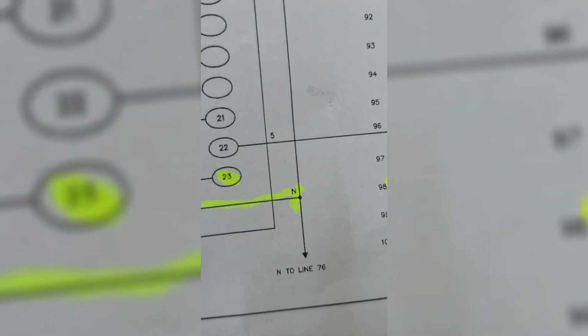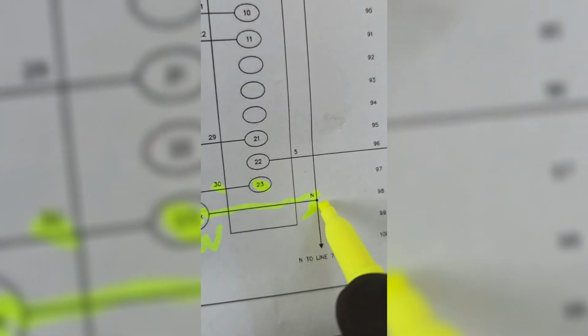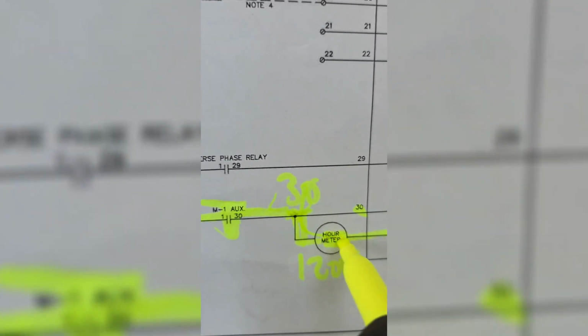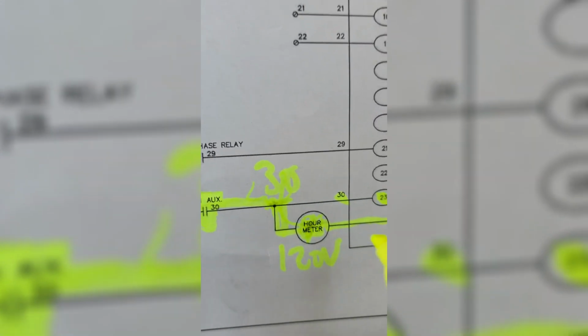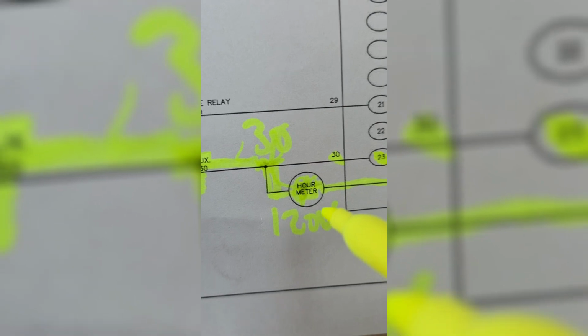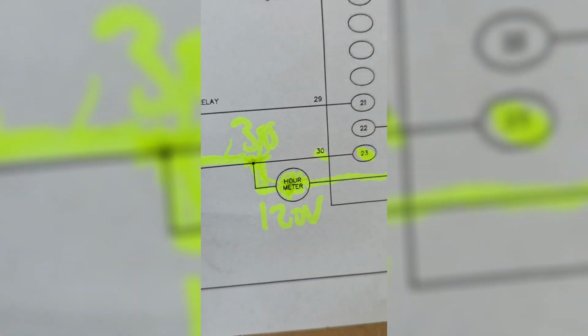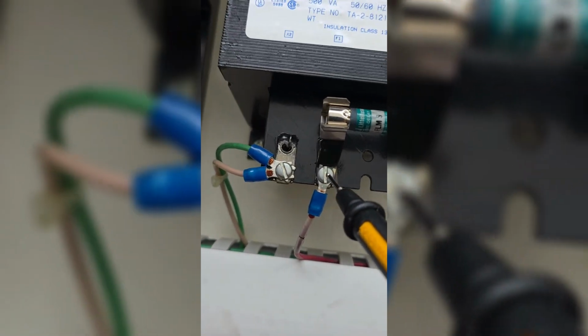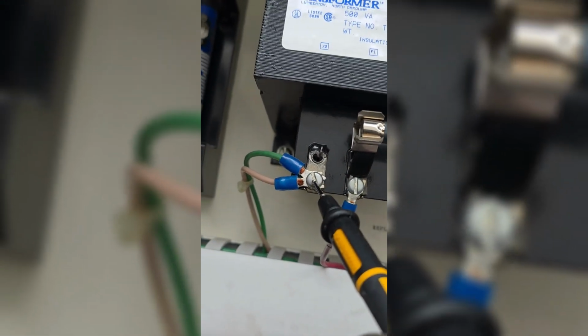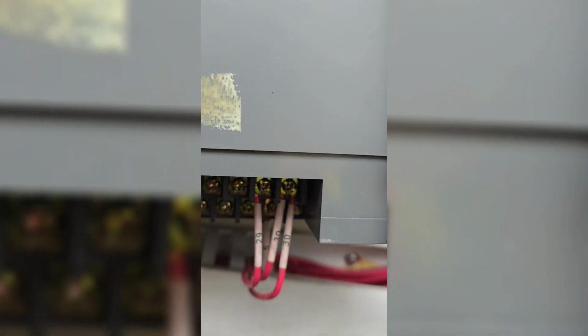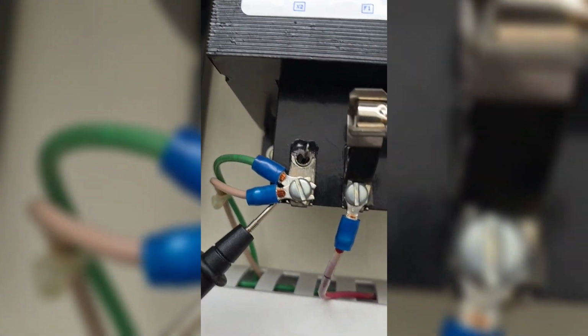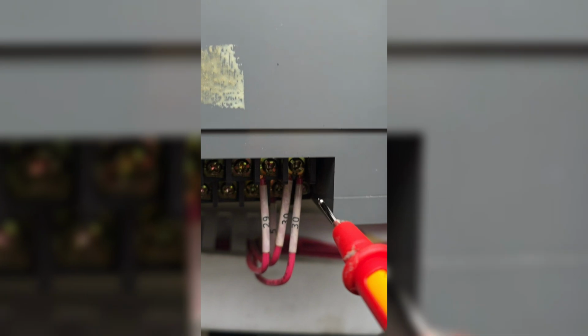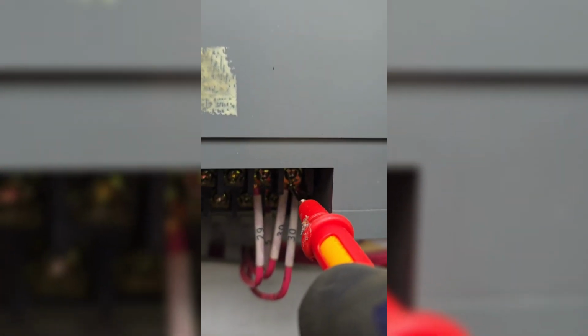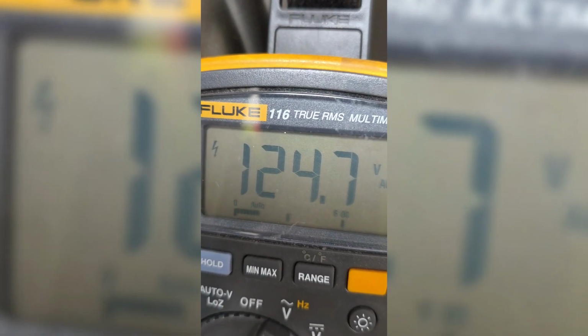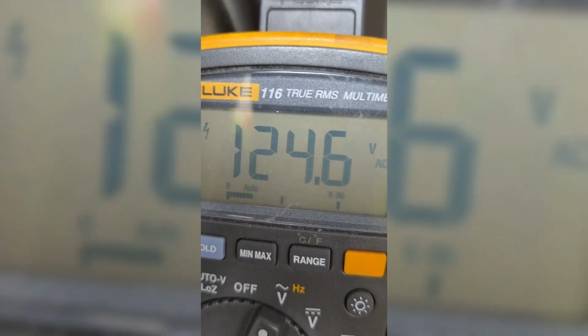If you remember what our schematic told us, we need a probe on neutral wire and wire number 30, and that should give us a 120 volt reading, which is going to tell us that we have voltage but our hours meter is not spinning. So here off of our step down transformer, this is our hot conductor and this is our neutral conductor. So we're going to probe this neutral and this wire 30 to see if we get voltage. I have one probe in our neutral, and the next one I'm going to put on wire number 30. And sure enough, our meter is showing a voltage reading of 124 volts.